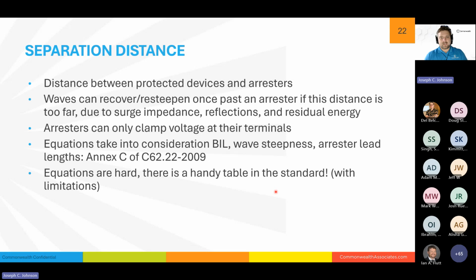So again, these equations for the allowable separation distance take the BIL, the wave steepness, and the arrestor lead lengths, and Annex C of C62.22 explains how this works. They're fairly complicated equations that I've noticed have some corner cases that don't always work. There is a very handy table, but it's only for single line, single transformer stations, so it doesn't necessarily help you. This is probably one of the more complex equations in this standard that I've seen. But again, it's a very important aspect. You can't just have an arrestor a mile away and think it's going to protect your transformer. It doesn't work like that.